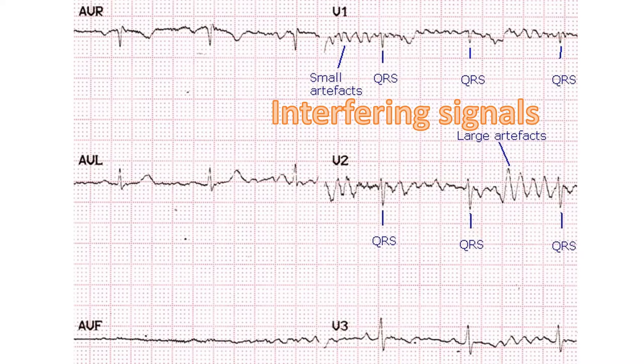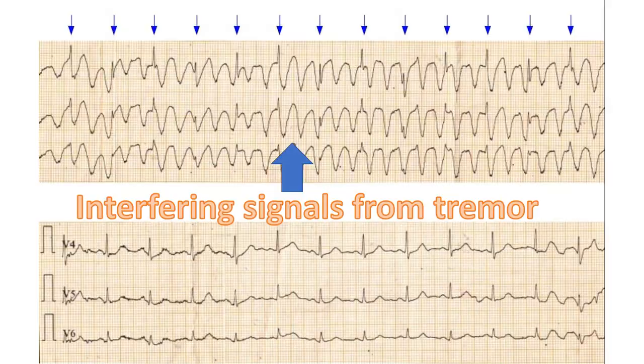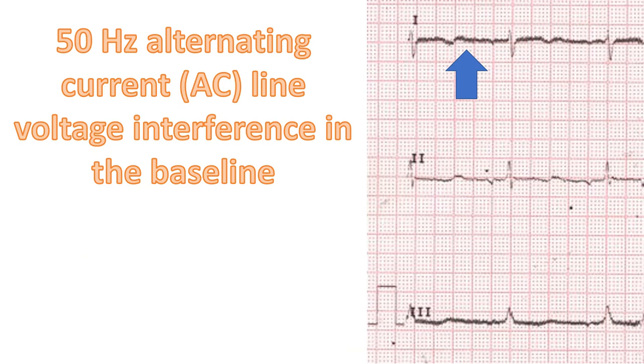As these signals are tiny, it is essential to avoid interference from other electrical signals in the vicinity and from the body itself. Electrical interference from within the body can arise from the electrical activity of contracting muscles, so the person must stay relaxed during ECG recording. Movements of limbs or even tremor due to anxiety can produce unwanted electrical signals, sometimes making interpretation difficult. This is common in small children, so recording ECG in children is done either during natural sleep or after sedation. Electrical equipment nearby may also need to be switched off during recording, especially in the hospital intensive care unit.